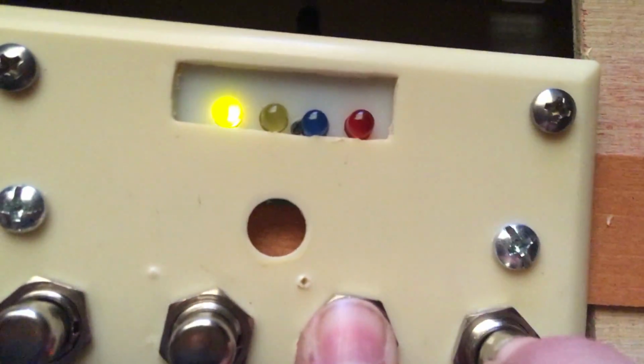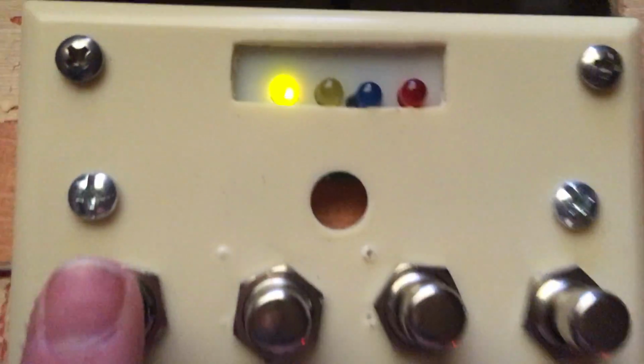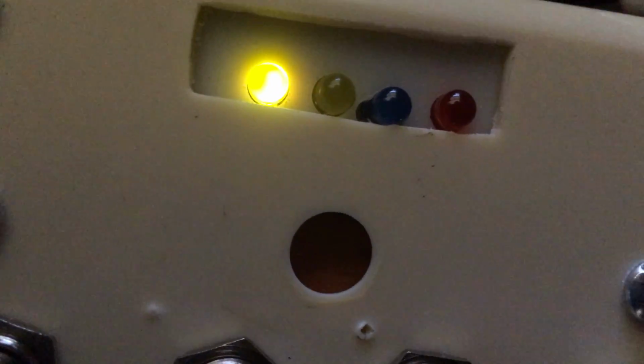So now let's try walk test. So you hold down the silence button when you restart, and now go into trouble because the walk test gives it trouble. So now this is zone 1. So it pulses once, so it's zone 1. And it does it every 5 seconds. I'll probably hear it again. Alright, there we go. So now, I'll try to activate zone 2 if I can, without blowing up the panel.